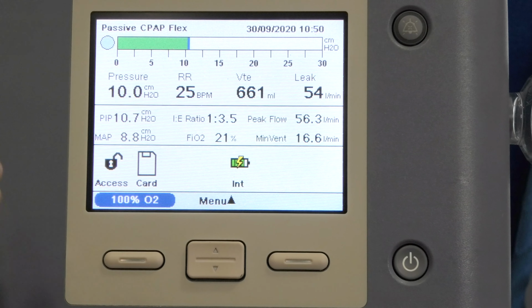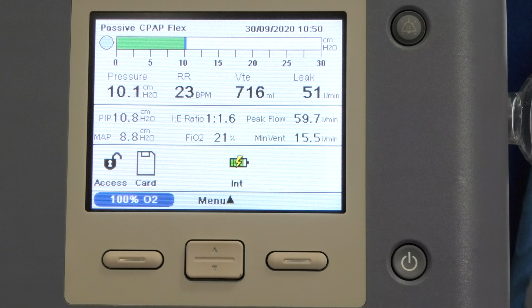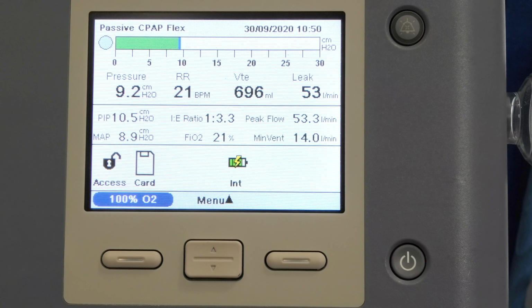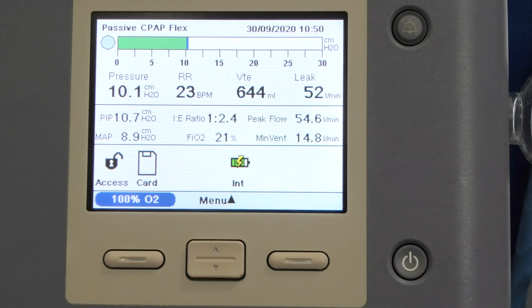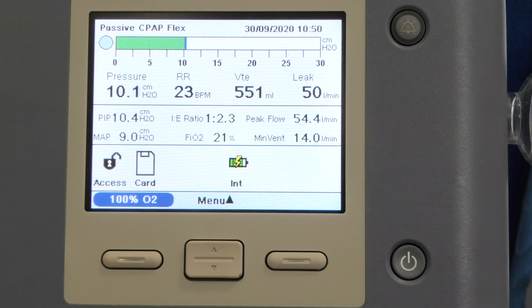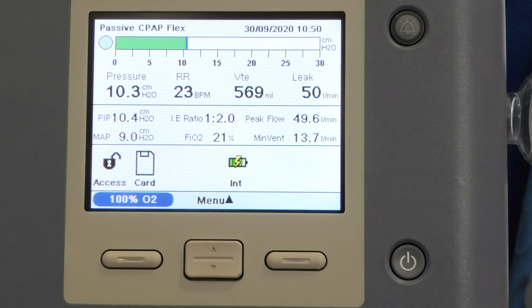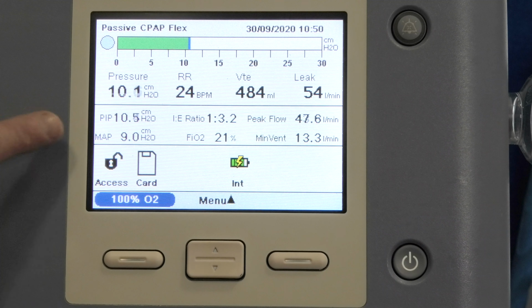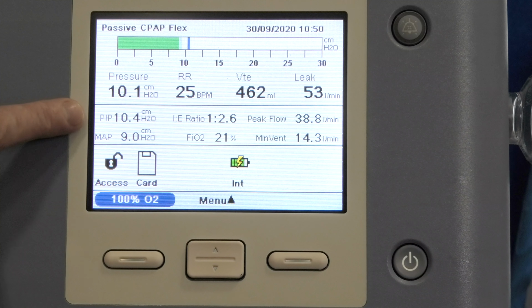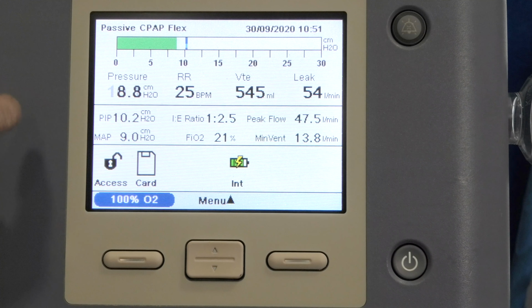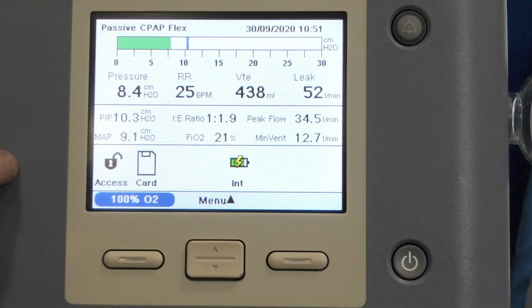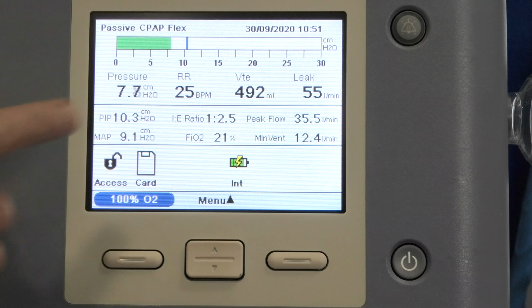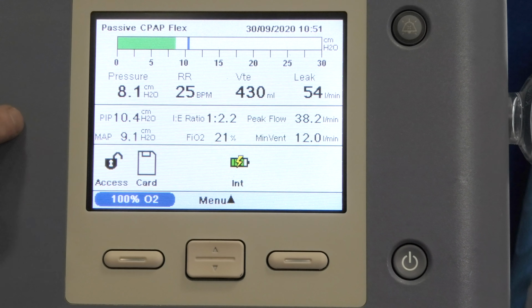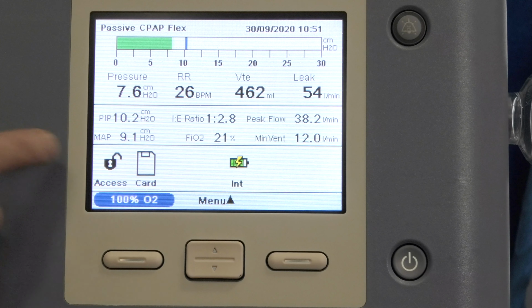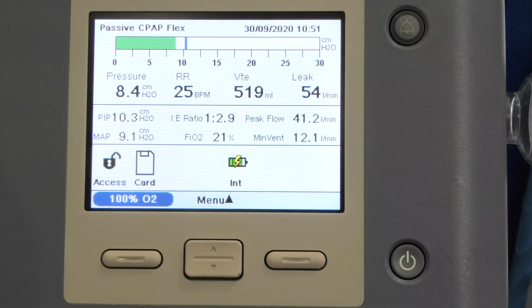In normal days, a leak of between 7 and 25 litres per minute is ideal. But the mask has to be comfortable on the patient's face. So a very, very tight mask with no leak probably won't be tolerated. So the least leak for the most comfortable mask is probably the rule of thumb. We have a lot of other information, such as peak inspiratory pressures, I to E ratios, peak flows, minute ventilation, and mean airway pressures. Because they're so variable in a non-invasive interface, the only thing we're interested in on that bar really is our FiO2, so how much oxygen is being delivered.